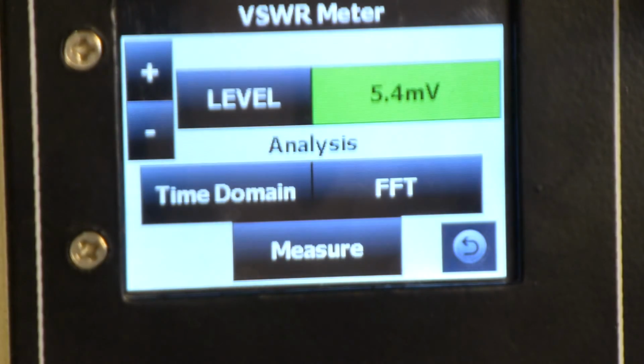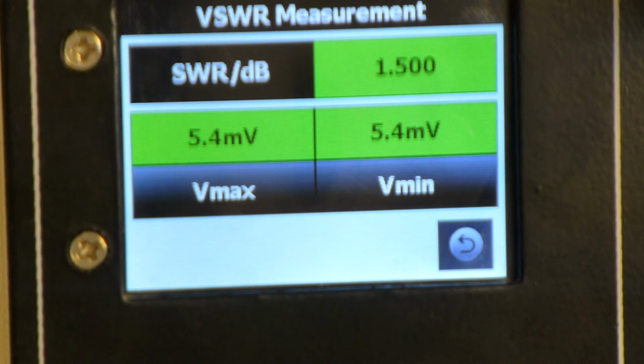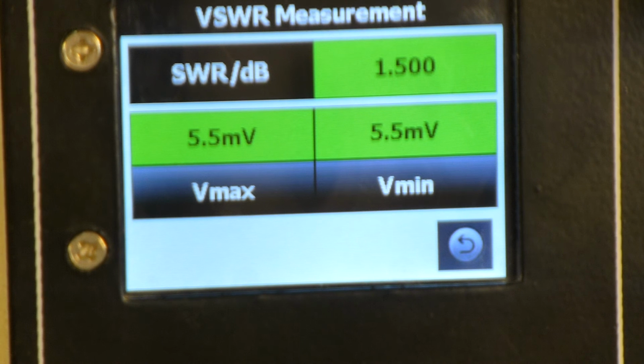Similarly, in order to do the measurement, we will press measure. Now right now it is reading a maximum voltage of 5.4 millivolt. Now for this setup, we have connected a short at port number 1, and by replacing it with termination, we will measure the difference between two readings and we try to measure the directivity of the coupler.